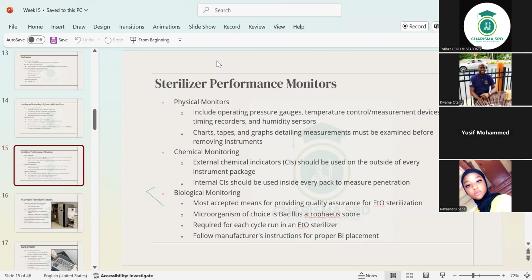When you take the wrap out and the tape doesn't show that it was well sterilized, the tape will not be well conditioned, so the color will not be as you're supposed to see. The tape manufacturer tells you that if you use it right, the gray color should turn black. If you take it and the gray color didn't turn black but is yellowish, it means something was wrong. Those are some of the physical monitors that you'll be seeing, and then the charts on the walls. Everything has been measured.